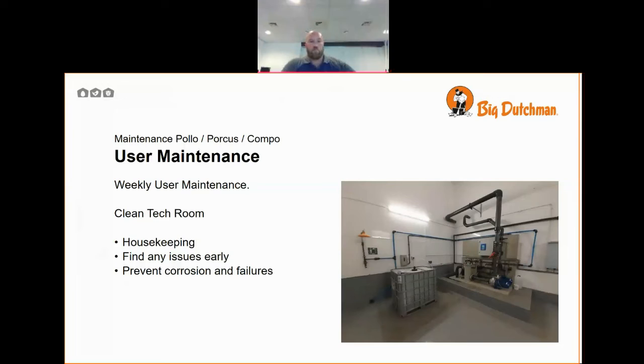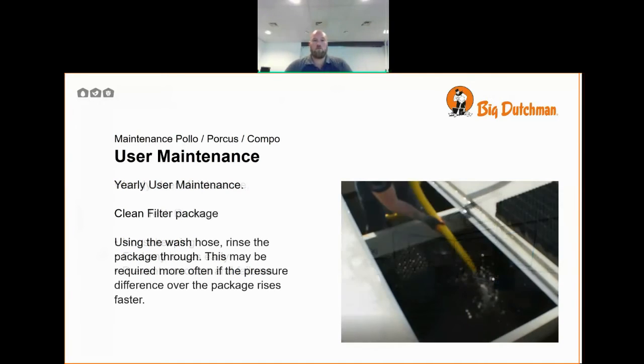And cleaning of the tech room. Good housekeeping in the technical room will help you find any issues early, and it will prevent corrosion and premature failures. Yearly maintenance. We class yearly cleaning filter package as yearly maintenance. Use the wash hose to rinse the package through. This may be required more often if the pressure difference rises faster.